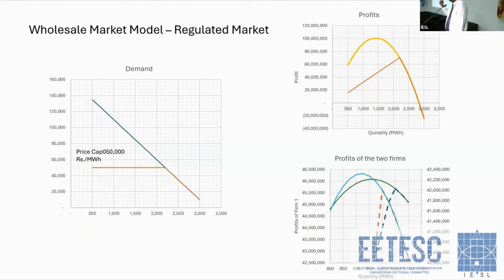The power system is not this simple, not even a glimpse of this. The first and simplest complication of the power system is the flow gates. You have certain transmission lines that you can't deliver more through than a particular rated value. So you must run a load flow in the background, and this optimization equation should operate on top of that load flow. That's what we call optimum load flow, where optimization is done together with load flow.